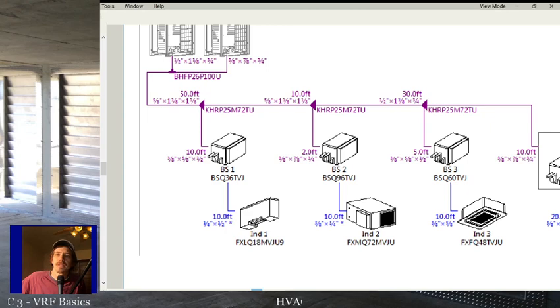So the sizing of VRF systems is kind of like you got to get just that Goldilocks number on the size of the line set. If it's too big, you're going to have oil return issues. If it's too small, you'll lose too much pressure or capacity. So it's imperative that it's calculated what the size of each piece of that line set needs to be.